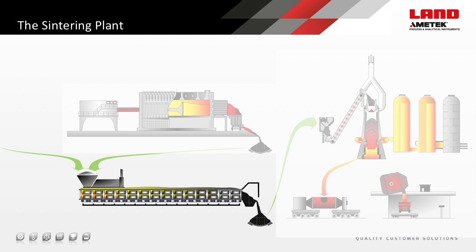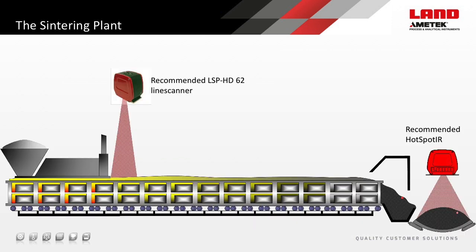The sintering plant receives a blend of iron ore, ore fines, calcium or magnesium fluxing agents, and coke fines. These are heated at the entry firing hood, and then the high-temperature layer propagates downwards through the cake by suction from below. The resulting sintered cake is fused with a more uniform clumped size, and is efficient and quick to react when charged into the blast furnace. Thermal imaging provides analysis and control for the heating zone propagation, with a Land LSP HD line scanner looking at the coke from above as it enters the sintering hood. HotSpotIR is then used on the conveyors afterwards to detect rogue hot spots that may cause belt damage or fires.